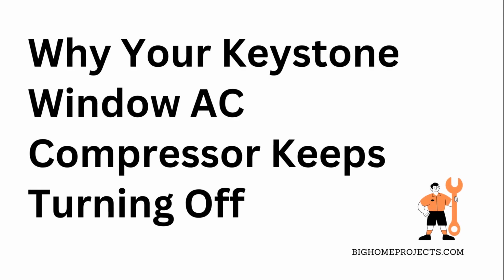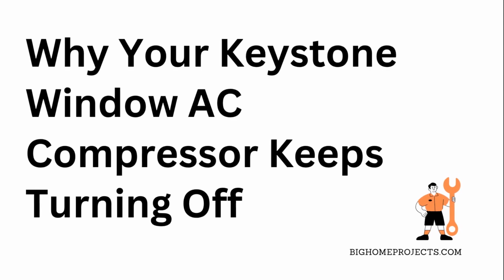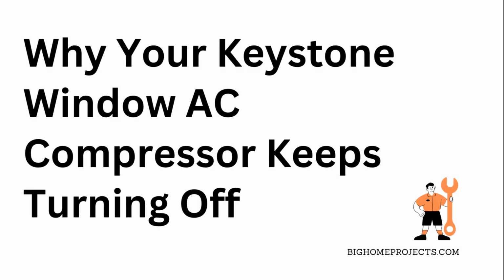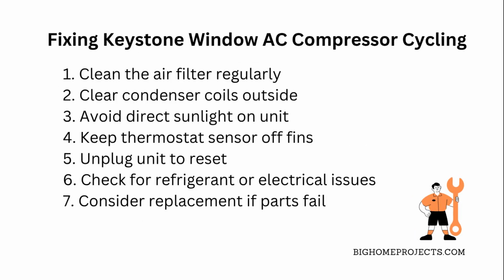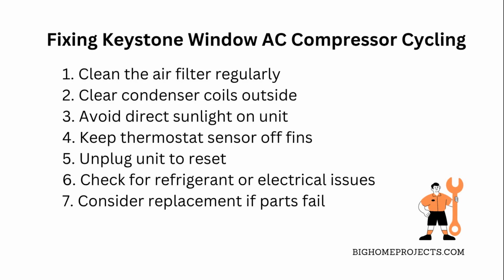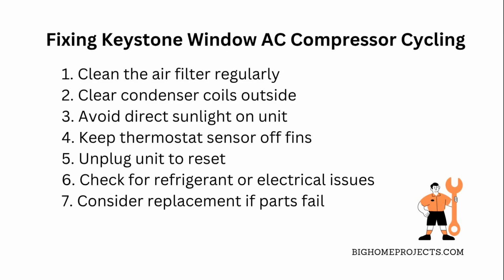If your Keystone window air conditioner's compressor keeps turning on and off every 10 minutes, that's a classic sign it's struggling to cool right or has some kind of issue. So, first off, make sure the air filter is clean. Dirty filters choke airflow and make the compressor work overtime.